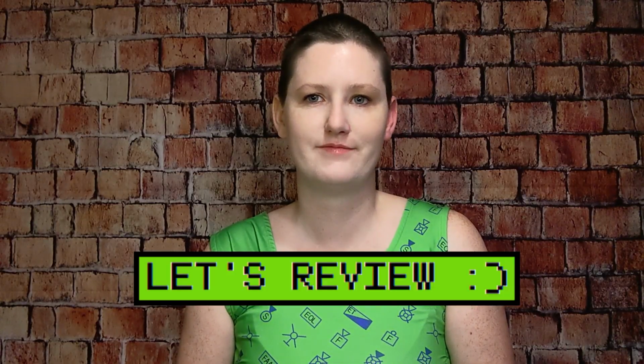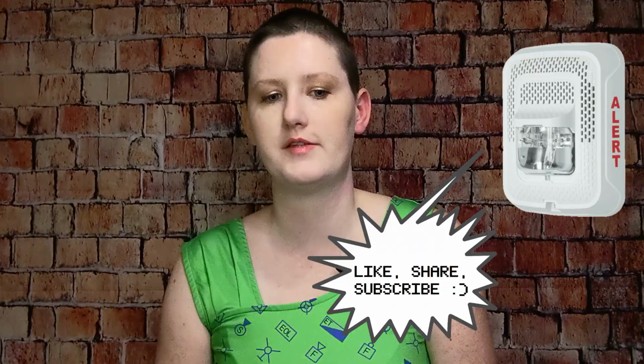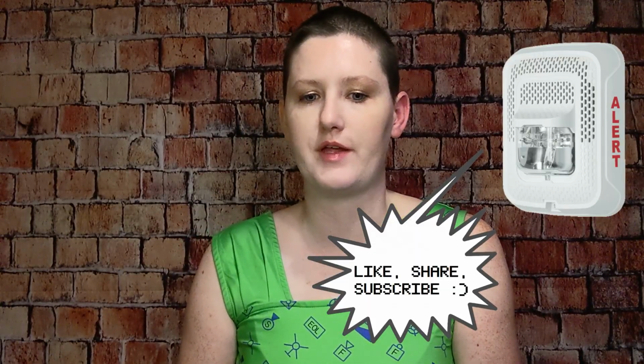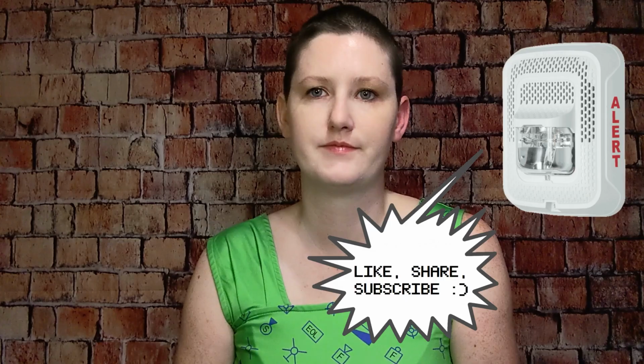Let's review. A notification appliance is a device that is intended to get the attention of the building occupants. They can include devices such as horns, strobes, chimes, bells, speakers, and textual displays, depending on the type of system that they're attached to. Typical fire alarm systems will usually have tone-based NAC devices. EVAC and mass notification systems will usually have speakers that issue verbal commands and will sometimes include textual displays for hearing impaired people.